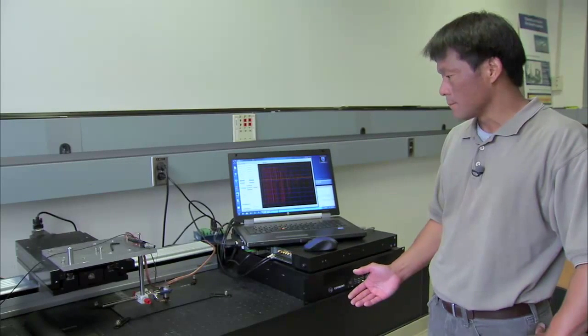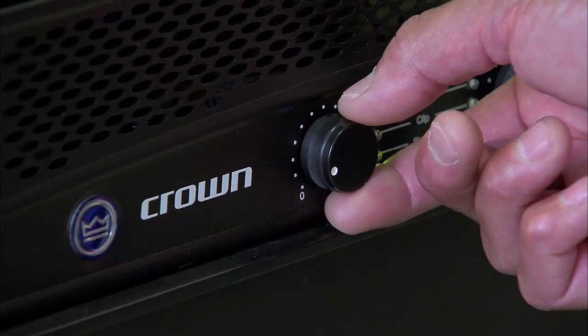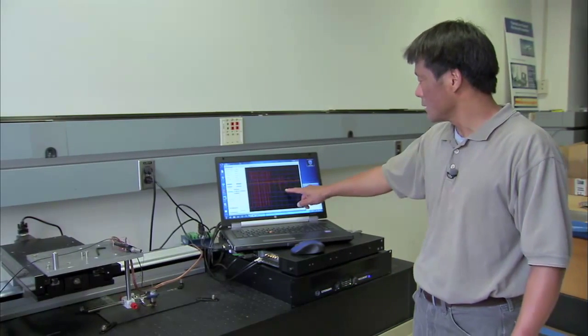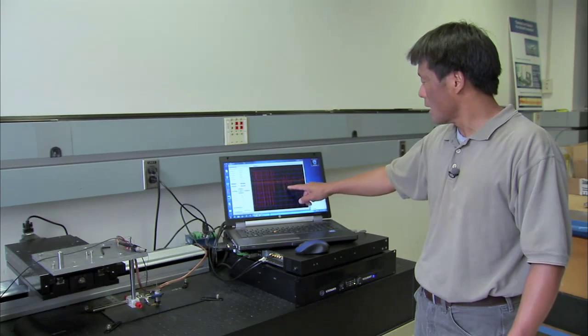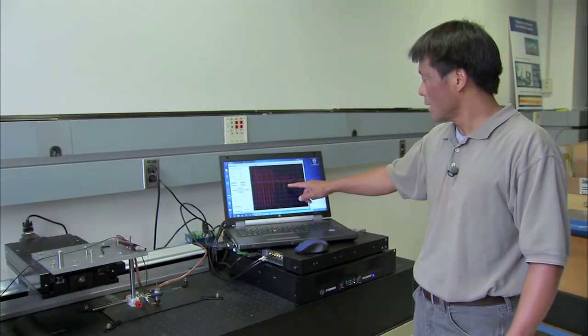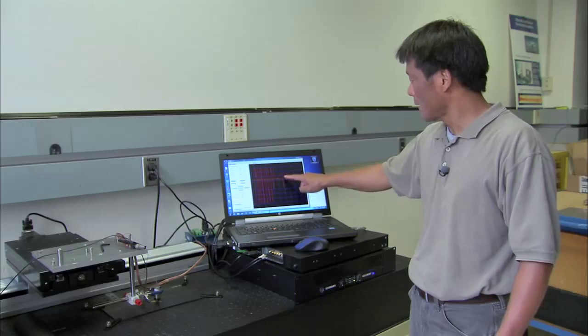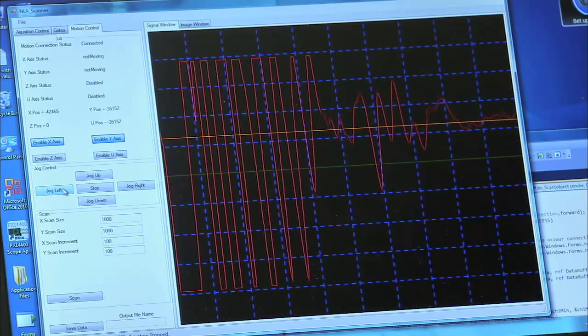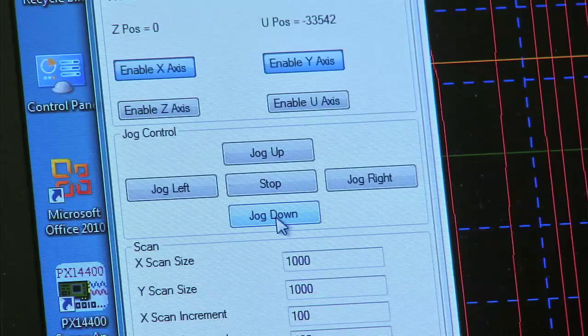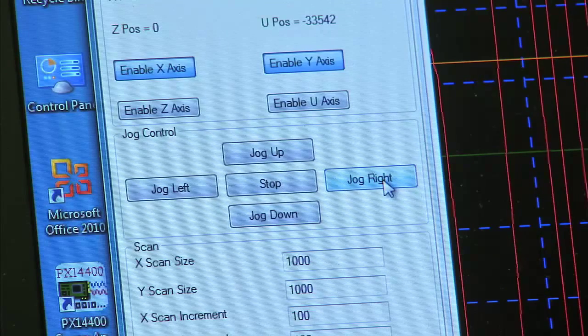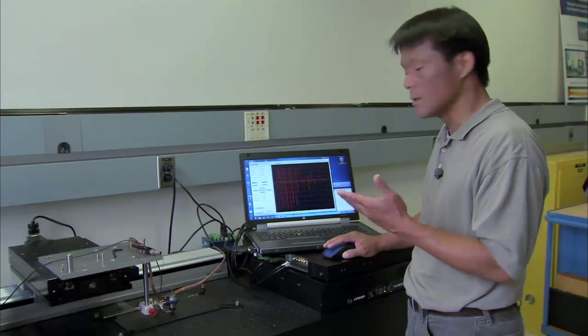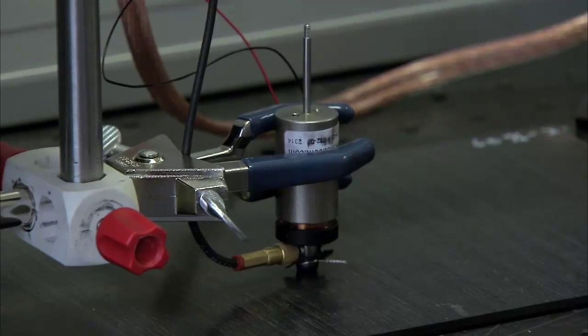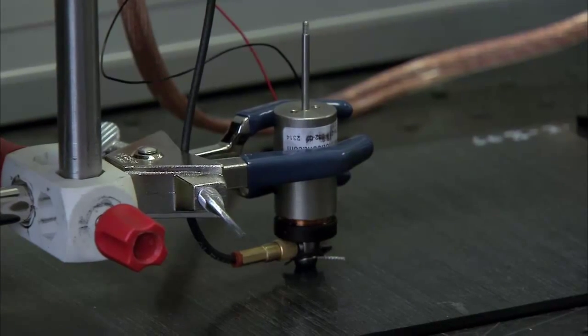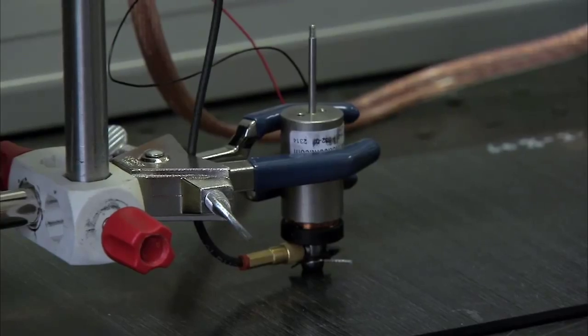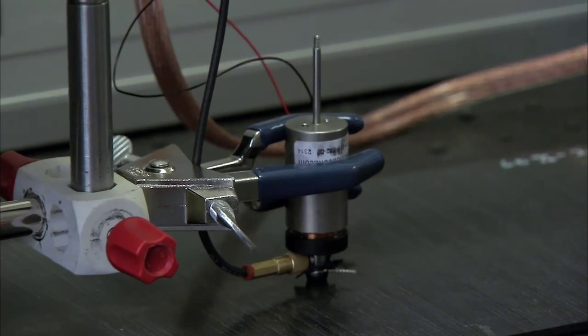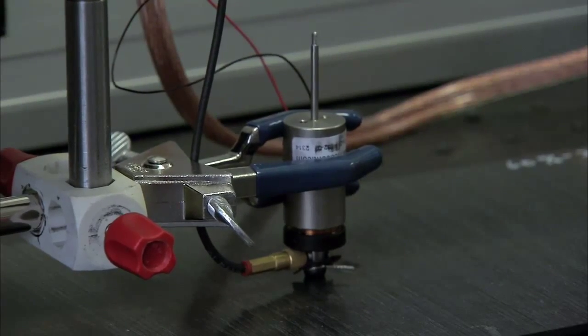So now I'll apply an electrical signal to the linear voice coil motor, and that will produce the signal that was shown previously, but instead of applying fingertip pressure, now we are modulating the transducer assembly electromechanically, and that's shown here. So we're getting ultrasonic coupling to the transducer solid membrane. Because it's vibrating on the surface, we can move the transducer and still get the inspection. So right now we're vibrating the transducer on the surface, and we can scan it to make multiple measurements on the surface. And the vibration allows the transducer to move on the surface, or in effect float on the surface.